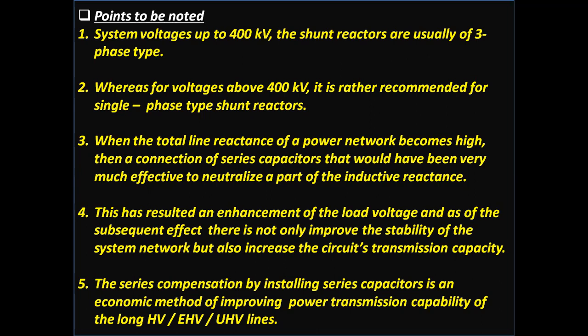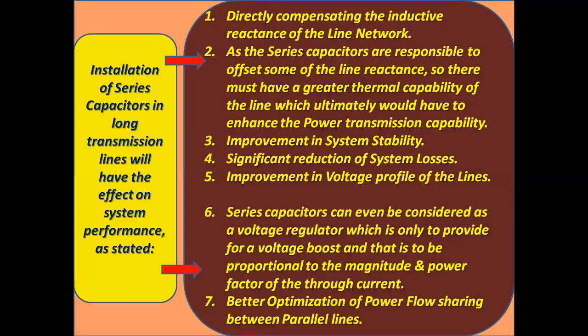Number 5, series compensation by installing series capacitors is an economic method of improving the power transmission capability of long high voltage, extra high voltage and ultra high voltage lines. Installation of series capacitors in long transmission lines will have the following effects on system performance. 1. Directly compensating the inductive reactance of the line network.